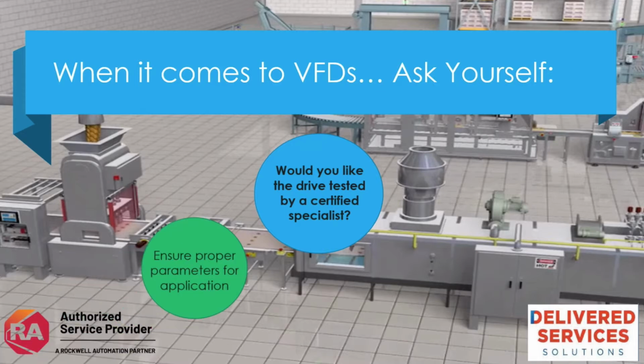Ensuring proper parameters for application. There are hundreds of parameters to program on an Allen Bradley drive. Most of those you don't touch, but getting someone certified on site to make sure that you have the correct parameters set up for your application. And verifying proper voltage and amp draw to the motor and on the line side, verifying that your drive is set up for optimizing longevity for your application.